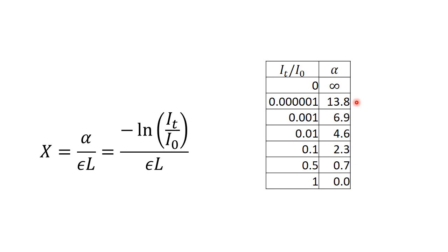Another thing to think about here is that presumably you're using some sort of a light detector to determine the transmitted intensity. And that means that as absorbance goes up, the signal going into your detector is going down significantly, but presumably the noise from that detector is going to be the same. So that means that as absorbance goes from a low number to a high number, your signal to noise ratio is getting lower and lower, and you're going to have a very high noise relative to your signal when your transmitted intensity is very low, and that is when you have a very high concentration of your species in your sample cell.